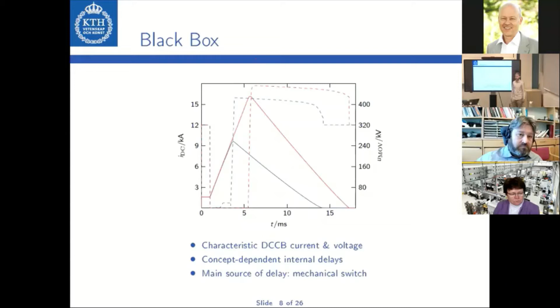Considering that the structure of the general DCCB is more complicated than an AC circuit breaker, it can also offer functionality in addition to interruption. An example is the auto reclosing operation. In a system that uses overhead lines, faults may be of a temporary nature, for instance, if a tree just touches an overhead line momentarily. The circuit breaker can then reclose and normal operation is resumed. Reclosing can be done by first reclosing the main path and then resuming normal operation, or alternatively by reclosing with the commutation path and commutating the current back to the main path for normal operation.